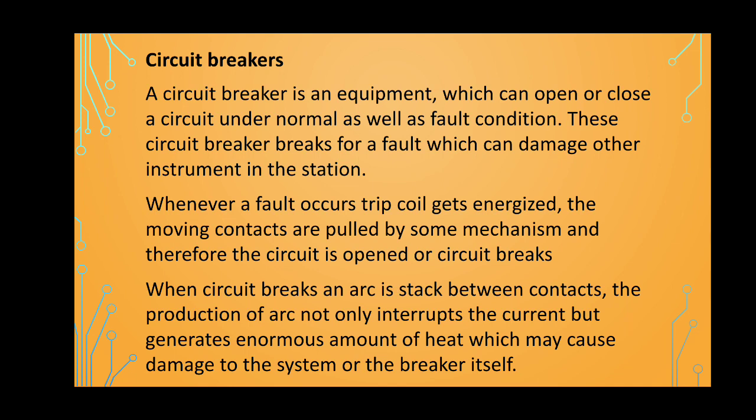Whenever a fault occurs, the coil gets energized and the moving contact is pulled by some mechanism, and therefore the circuit is opened or broken. When the circuit breaks, an arc may be struck near the contact. The production of the arc not only interrupts the current but generates a large amount of heat in that space, which may damage the system or break down the breaker itself. So this is also required in electrical power systems as the circuit breaker.